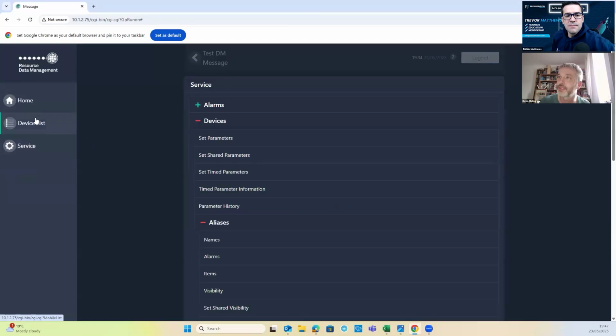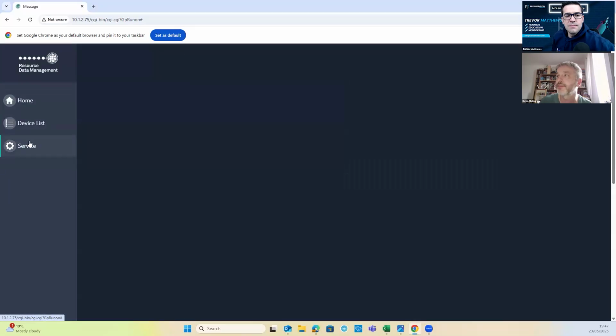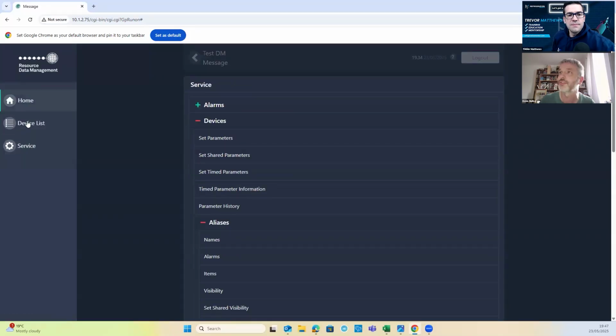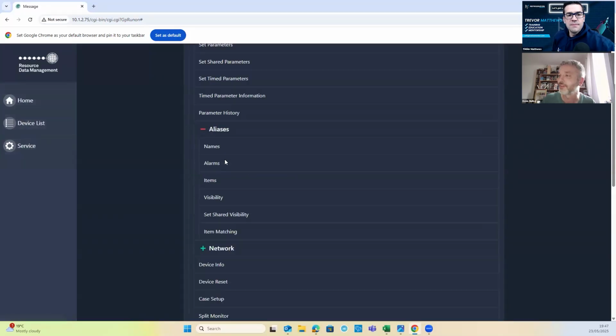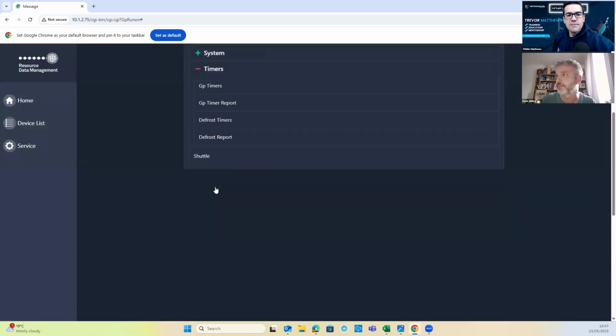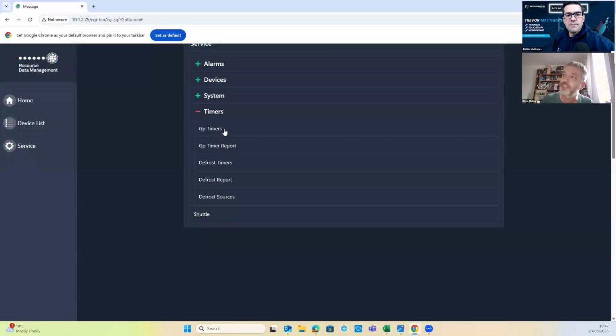In the wrong one, if I went into the right one, it would help. In the front end, you've got a timer option. You can ask the front end to do all your timers for you, for lights in GP timer and for defrost in defrost timers. So if you've got 100 fixtures, you want to do them all nice and neatly, set them up on the data manager, and set the controller to get remote defrost.